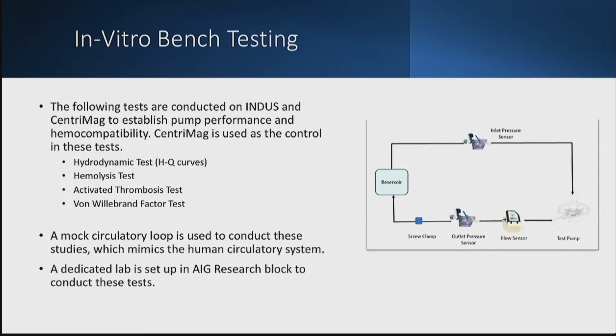At AIG, we have a dedicated research lab for conducting in vitro bench testing on these injection molded parts. On the right-hand side, you can see a mock loop set up in this fashion, where the inlet of the pump is connected to a reservoir, and there is a flow sensor and two pressure sensors connected to the loop. Any test pump can be connected in this loop to conduct hydrodynamic, hemolysis, activated thrombosis, and von Willebrand factor tests.